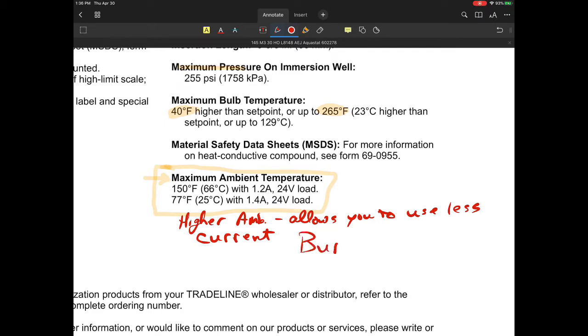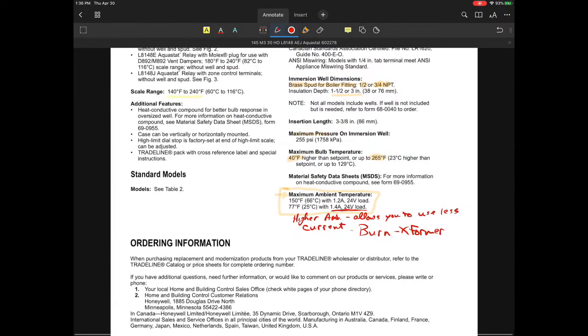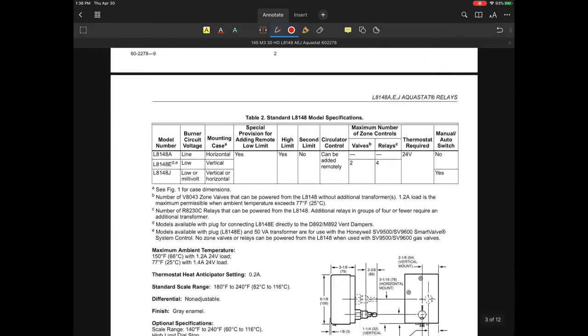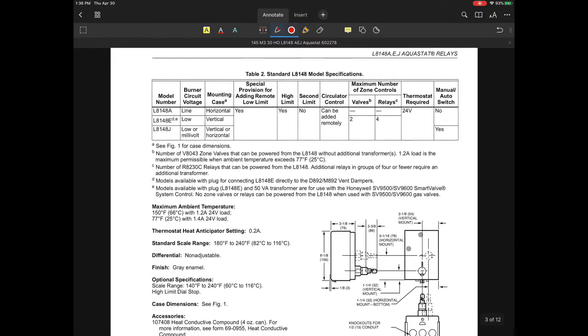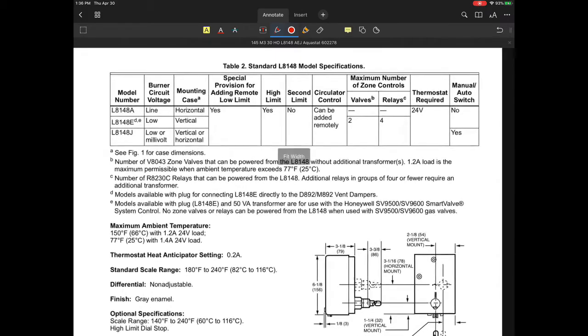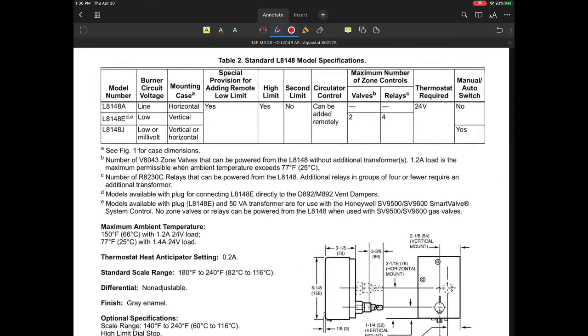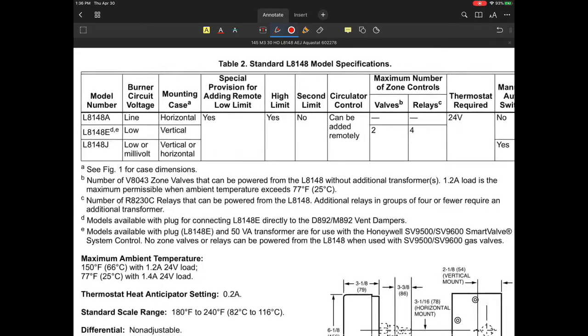What they're worried about is if you have a mechanical room or a boiler that is emitting so much heat out to that Aquastat, you potentially could burn out the transformer. That's the concern of why they are identifying that. Again, rarely does that become a problem, but it is something you have to be aware of. I've been in commercial jobs where the mechanical room was 120 degrees at times, and that gets very challenging for a lot of those things. So let's move on.